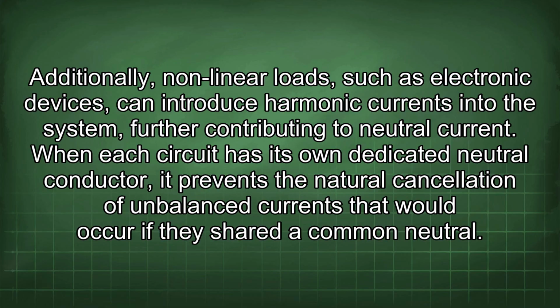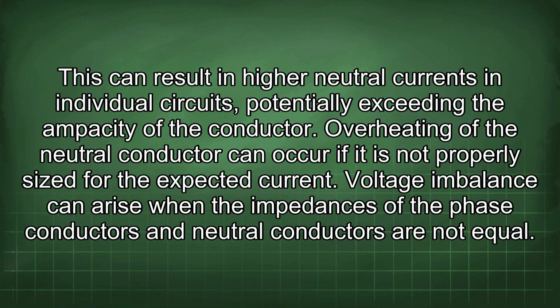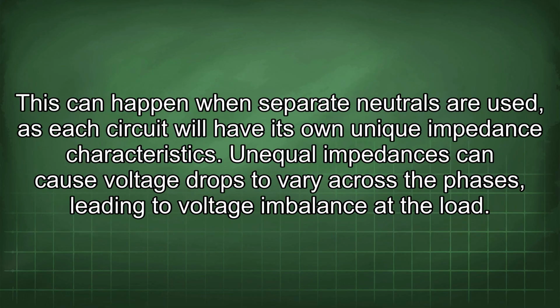When each circuit has its own dedicated neutral conductor, it prevents the natural cancellation of unbalanced currents that would occur if they share the common neutral. This can result in high neutral currents in individual circuits, potentially exceeding the ampacity of the conductor. Overheating of the neutral conductor can occur if it is not properly sized for the expected current. Voltage imbalance can arise when the impedances of the phase conductors and neutral conductors are not equal. This can happen when separate neutrals are used, as each circuit will have its own unique impedance characteristics. Unequal impedances can cause voltage drops to vary across the phases, leading to voltage imbalance at the load.